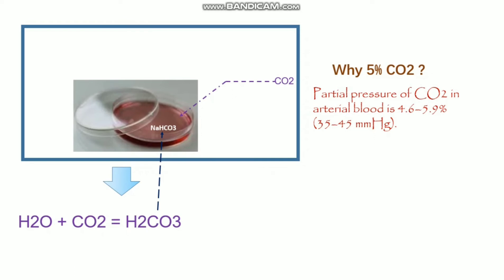The next question is why 5% carbon dioxide? This is another important question. The partial pressure of carbon dioxide in arterial blood is around 4.6 to 5.9%, equivalent to 35 to 45 mmHg. This is why around 5% carbon dioxide is maintained in most cases in the incubator.